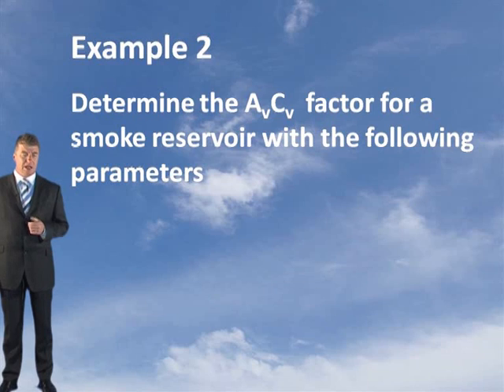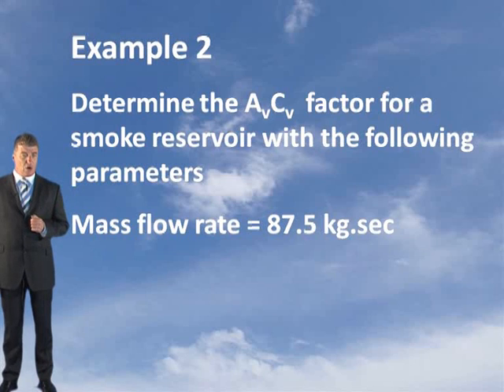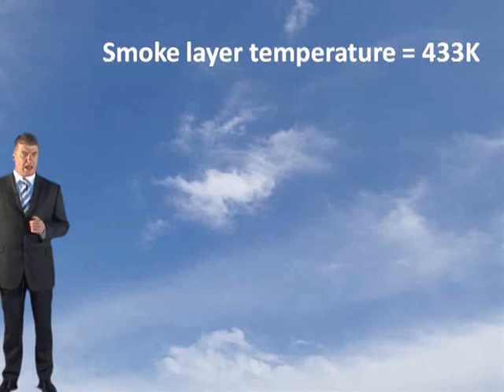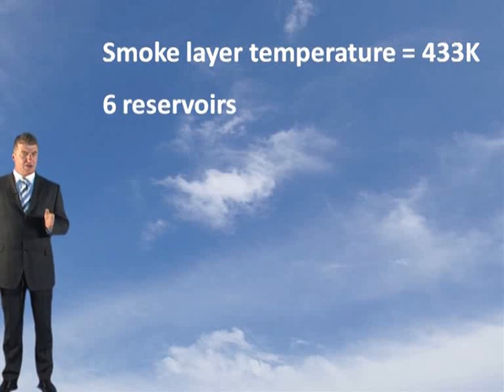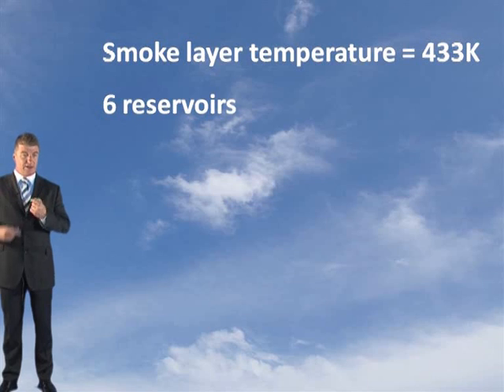Let's do another example using this method. Determine the AVCV factor for a smoke reservoir with the following parameters. Your mass flow rate of smoke is 87.5 kilograms per second. Your density of air is 1.177 kilograms per meter cubed. Your temperature of the smoke layer is 433 degrees Kelvin. Now there are six reservoirs available, so when you come to your AVCV factor, you should put in 1 divided by 5. As long as they're all available and going to open, you've got one for your outlet and five inlets.